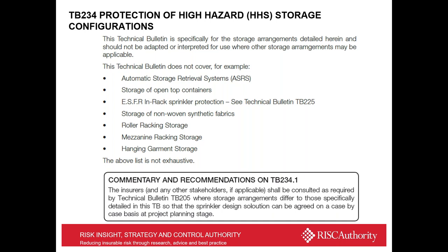And the recommendation is that if you come across any other storage arrangement that's not covered by TB234 or falls into this list, you should then consult the insurers and any other stakeholders on how to sprinkler protect these. They may decide to use an NFPA or FM solution, but what we can't be doing is adopting a standard to make it fit a certain storage configuration. So this requirement came in just so that it's now incumbent on the sprinkler contractors to make early consultation with the authorities to find out, work out, and come up with a storage solution that doesn't fit within TB234.